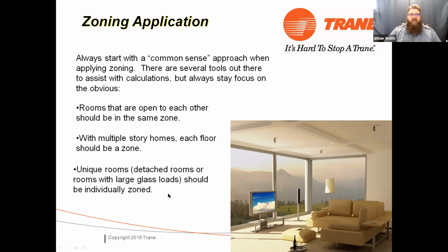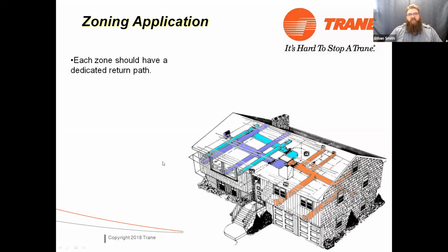Those rooms we need to treat as individual zones as well. Okay. So here's the other rules. When we start talking about ductwork, each zone has to have a dedicated return. That return needs to be sized to handle all the air that is going to be put into that zone. So if you have a zone that's delivering 600 CFM when it's calling, you need to have 600 CFM of return. If you've only got 500 CFM of return, you're only going to get 500 CFM out of your supply because you will pressurize that zone. So make sure that we've got returns for each zone.